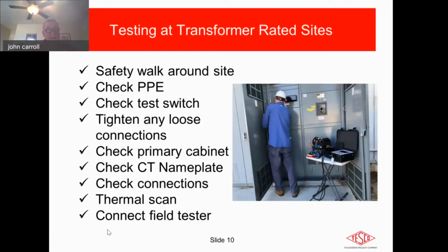If they can, and they do, in this case, this gentleman was doing this really very carefully and very thoroughly, tightening any loose connections they may have, checking the test switch, opening up the primary cabinet safely, checking the nameplates on the CTs, and even to the extent of doing a little thermal scan. That's impressive. It's a little small thermal camera.